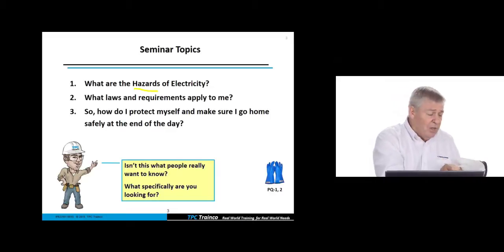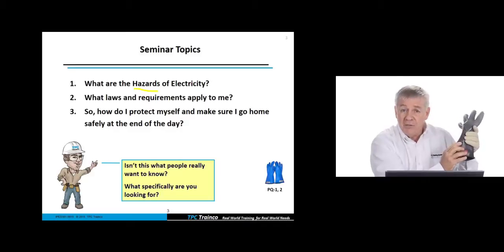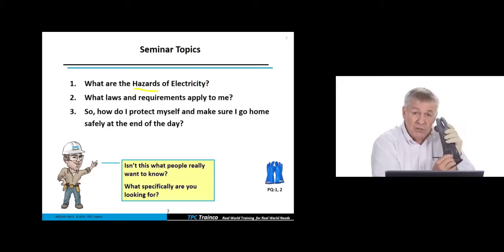And remember, before each day's use, we have to give this rubber an air test. So we would purchase an inflator, pump some air into here, hold it against my cheek, make sure there's no air coming out. And that would be very good to make sure that my workers did not receive a shock.